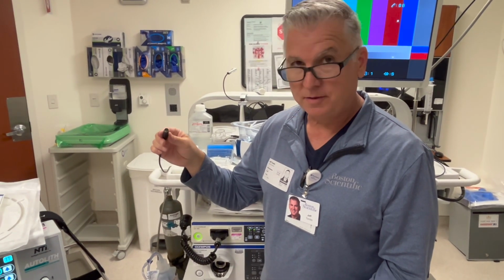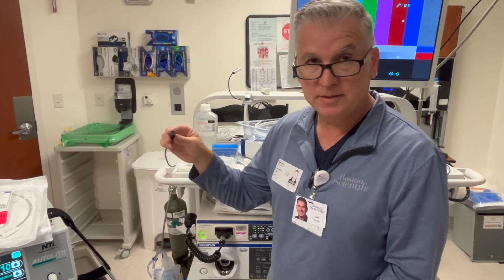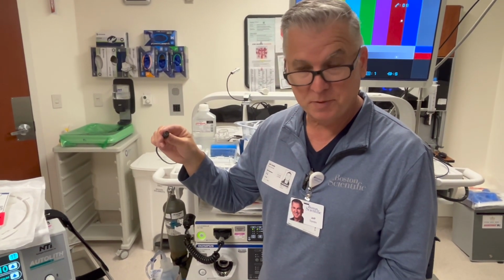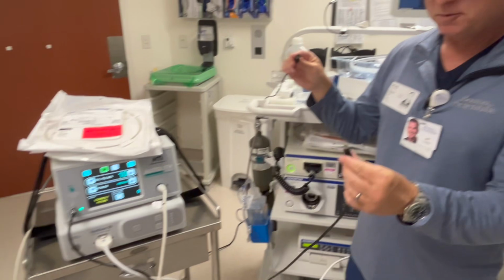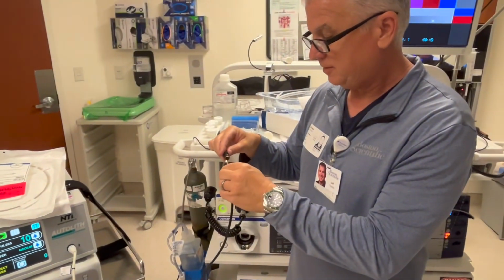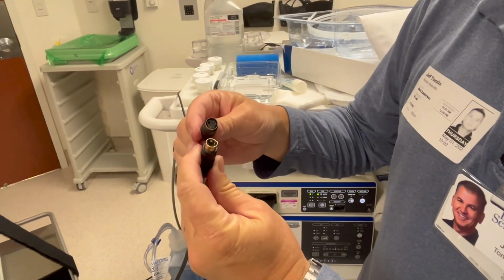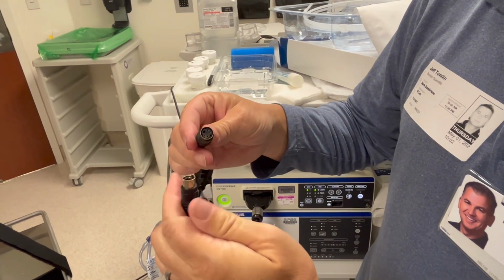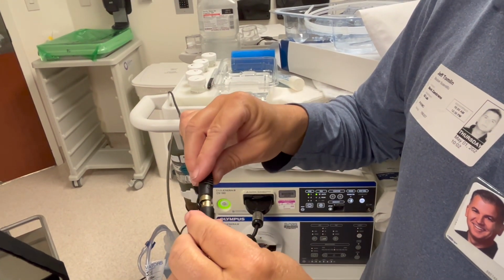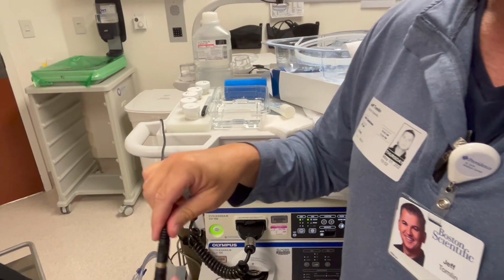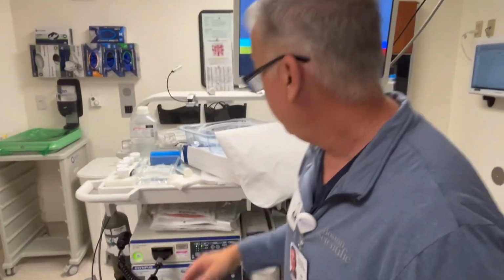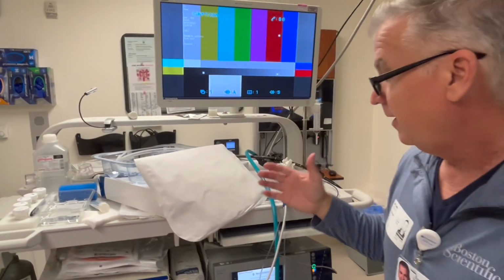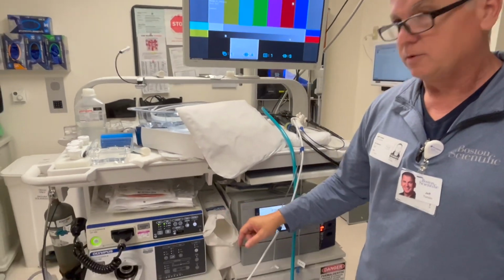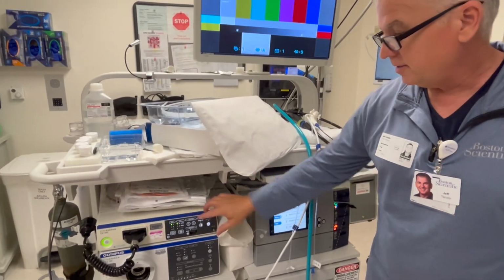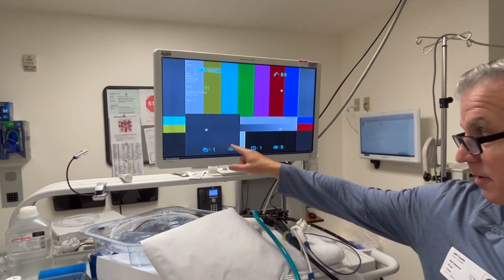Here we have a cable that's already plugged into the back of the processor for picture-in-picture. The cable coming from Spyglass, we want to connect to our picture-in-picture. It's important that we line the pins up, and you don't want to force this. It should just go right in. Once we have connected our picture-in-picture, the way to toggle through that is with Custom 1 and Custom 2. Custom 1 will turn on the picture-in-picture.